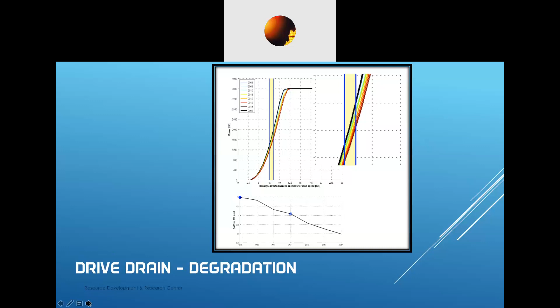Derating: each component has its own temperature curve to operate. When it crosses that limit, some of the components directly influence or control the turbine's operation. At that time it is going to influence the power rating. That is what we call derating, meaning we are forced to operate at a lower power level due to some internal safety or performance issues happening in the turbine, or sometimes it is external also.